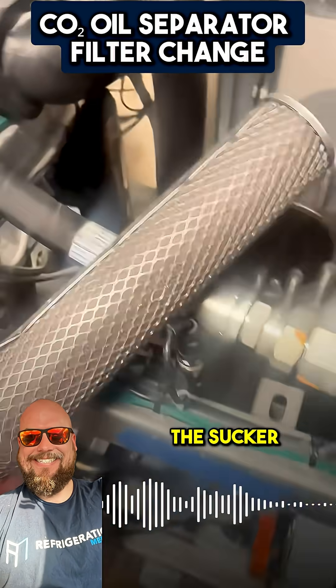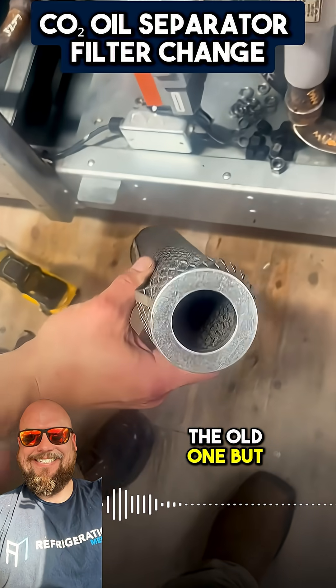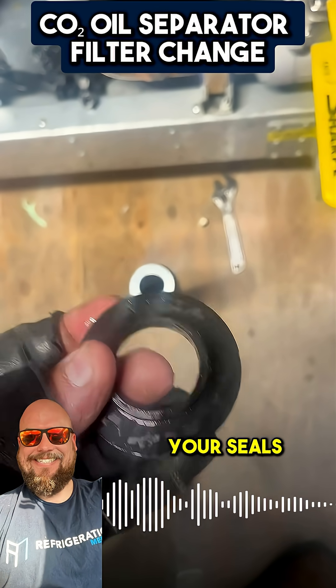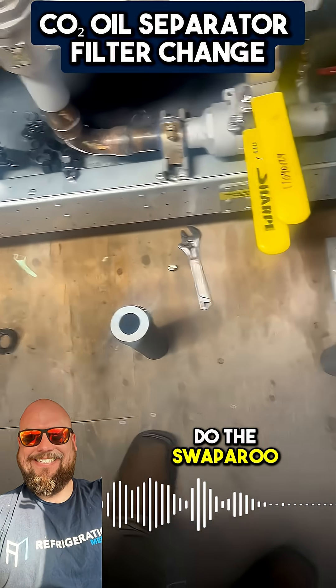We're going to replace this. What we did was — these are your filter caps. We've got to make sure that you take them off. See how that one does not have it and that one does? That's the new one, that's the old one. So we're going to go ahead and replace this. Just make sure you take your caps and your seals off the old filter.